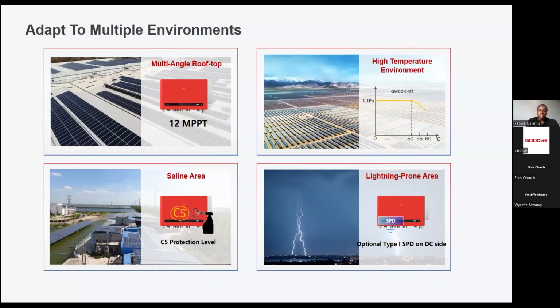Mention that our inverters do have 110% AC overloading, output AC overloading. And I gave an example of the HT 100 kilowatts. Temperatures below 45 degrees will allow the 100 kilowatts to generate an additional 10 kilowatts of power generation. So the 100 kilowatt will be giving you 110 at temperatures below 45 degrees.